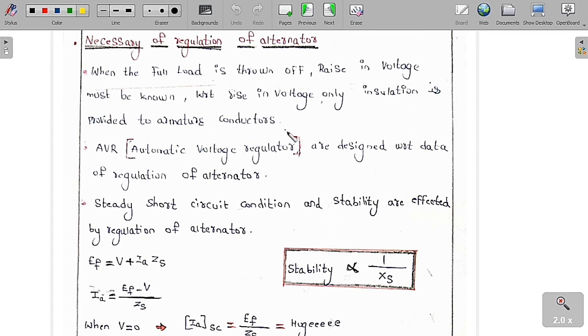And I already told you, suppose you keep a full load across the alternator and suddenly the load is thrown off. If you take the load off with the open circuit, which we can call the no load condition, the voltage will rise. So how much the voltage rises must be known. Based on that only, you provide the insulation to the armature conductors. If you don't know that, then you don't know how much insulation is required. Definitely, you should know the regulation. Then only, based on that, you can provide the insulation for the armature conductors.